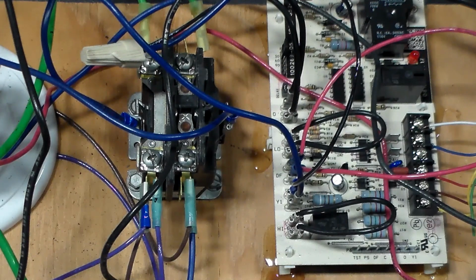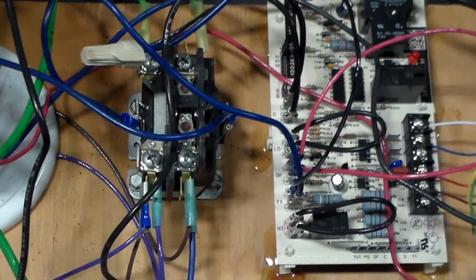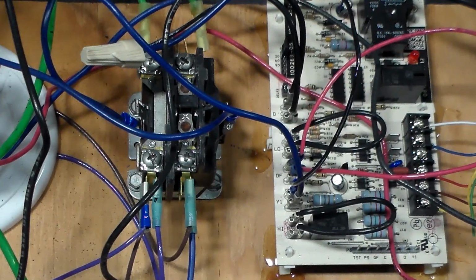In this case, we want to turn the fan off because, as we should know, the basics of a heat pump: when it goes into defrost, it basically flips into cooling. So the board will flip it back into cooling, so the outdoor unit now becomes the condenser again, and it's going to be getting hot. And we want that head pressure to get higher because it's cold outside, so we don't want it running in a low ambient air conditioning kind of a situation. So it's going to cut the outdoor fan during defrost. So there's always going to be a fan hookup here on the defrost board for the defrost board to turn off the fan during defrost.